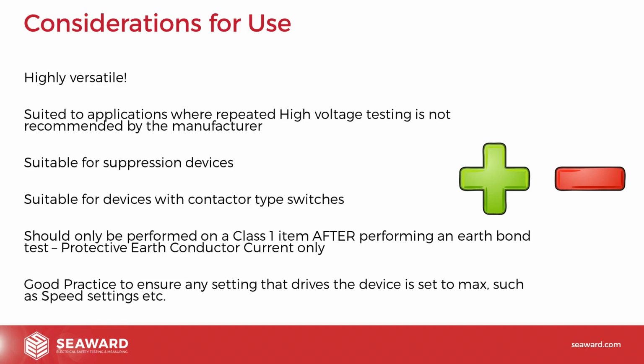Now, good practice when performing either a protective earth conductor current test or a touch current test is that we always ensure any setting that drives the device is set to its maximum. So if you have any kind of dials for speed settings, if you have any multi-switches for things like elements, so if your radiators have multiple switches to switch on all the elements, we'd recommend certainly, if you can, switching them all on so that you're really driving the device at its max, and therefore any leakage would be at its maximum too.